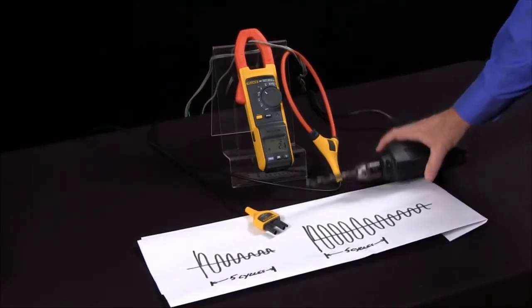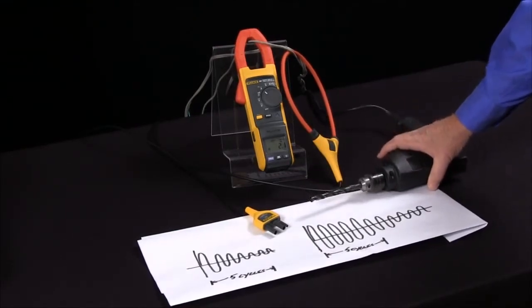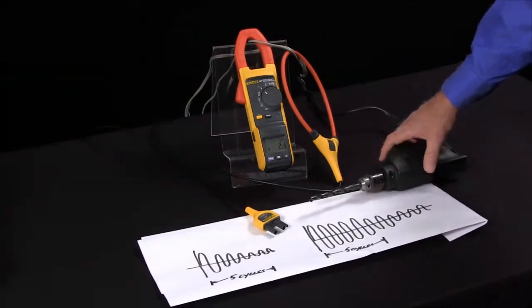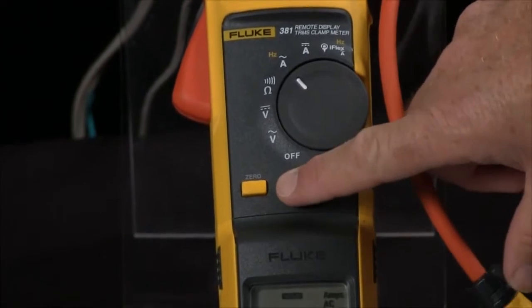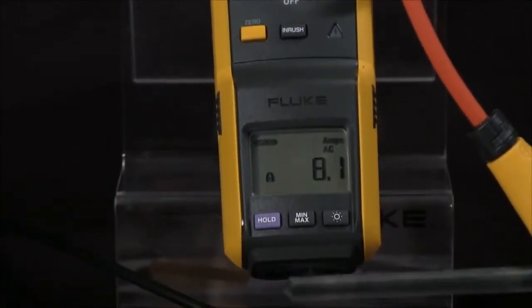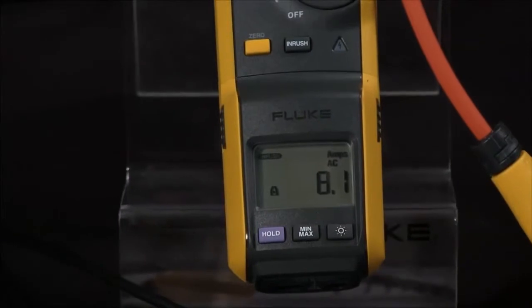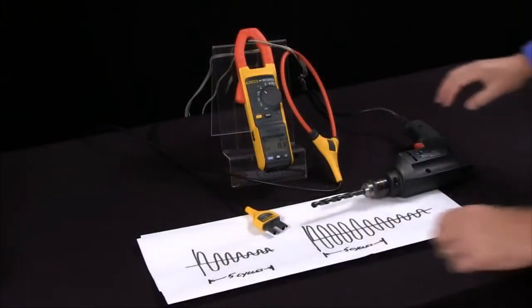To use the 381 to measure inrush current of a motor or other type of mechanical device, what we first do is turn it to amps and then press the inrush key. The meter will wait for you to start the motor and will be able to capture the inrush current.